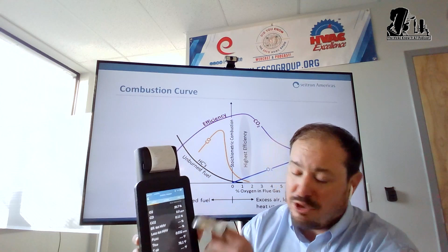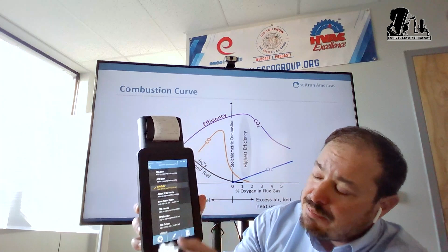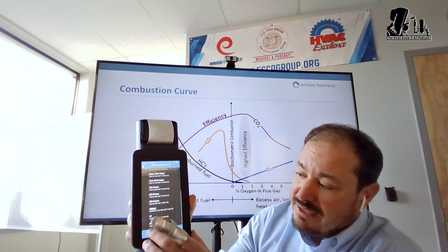What my guys can do is use what we call Pro mode, but I call it the combustion assistant. Instead of looking at the numbers and having to decipher it, in Pro mode I can choose equipment from a long list of different types: 90%, 80%, 70% atmospheric water heaters, condensing water heaters, furnaces, and the like. You can even add a specific range based on your manufacturer's requirements, since sometimes they're much tighter than the general rule of thumb I give you.